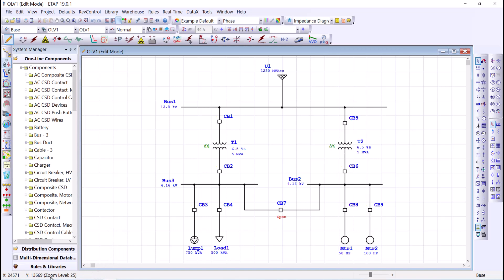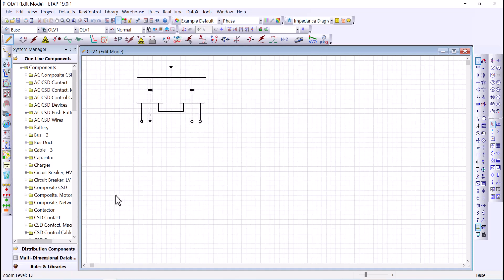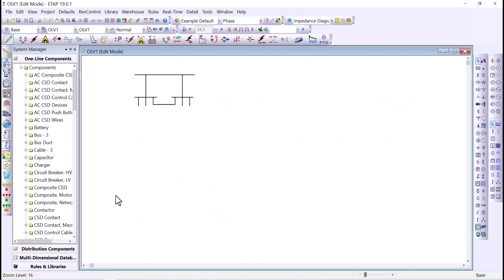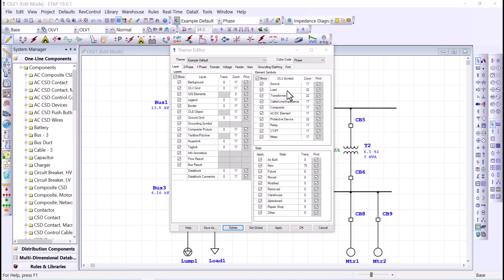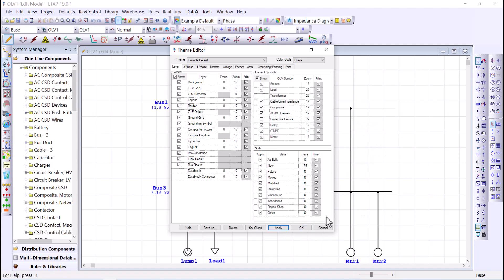Let's test that theory — the zoom level is 25. Zooming out to 18, then 17, the grid is still showing at zoom level 17 or higher. Going down to 16, the grid is no longer showing. I can now take this concept and apply it to other component layers, showing or hiding protective devices, transformers, relays, CTs, or VTs at specific zoom levels, then pressing Apply to simplify the one-line diagram.